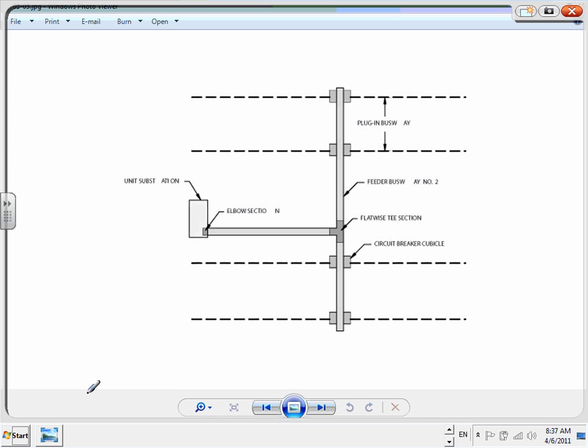We're going to have a feeder busway, a 1,000 amp feeder busway. And I want to remind you, Brad, that you need a 1,000 amp overcurrent protection device. So here's a typical busway, 1,000 amp coming from the switchgear. Very typical to your project, guys. A 1,000 amp busway feeder, and this 1,000 amp is going to split, as you can see, all the way.